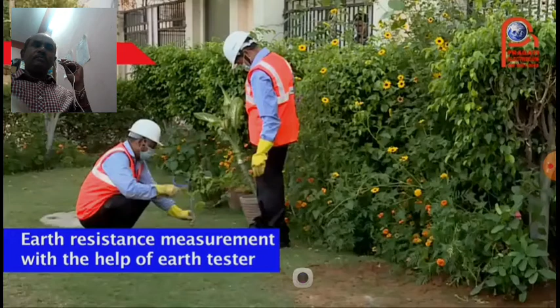Earth resistance measurement with the help of an earth tester. Now we can see how they are using the Megger for measurement of earth resistance. So these are the two spikes placed in a straight line, and C1 and C2, P1 and P2. Here C1 and P1 are connected shortly, and the two electrodes are at equidistance, provided in a straight line.